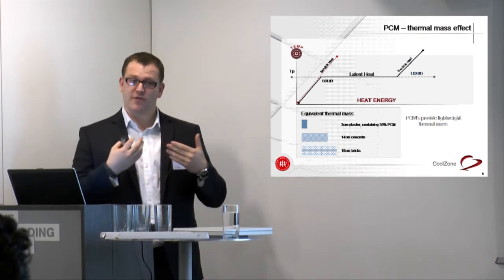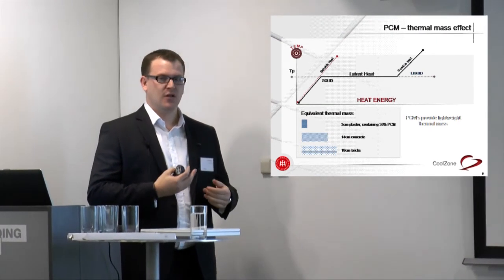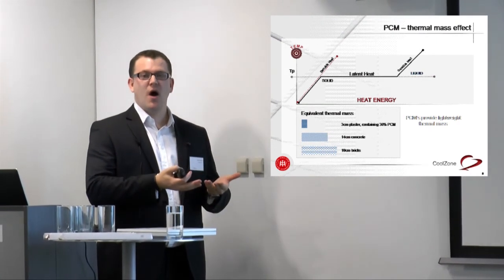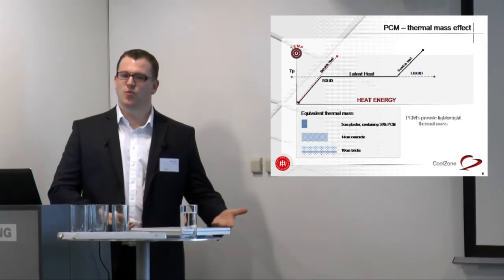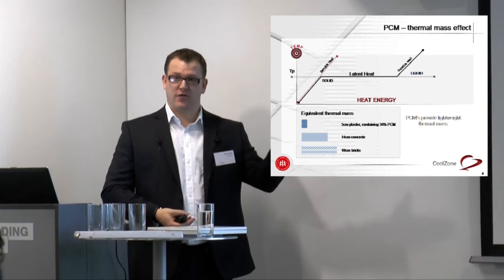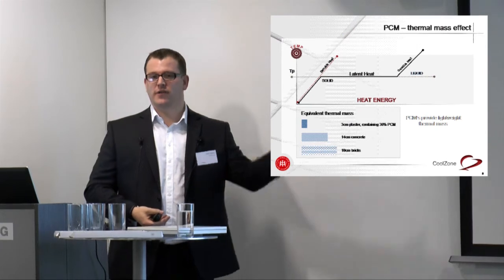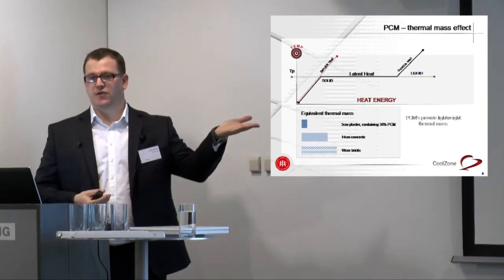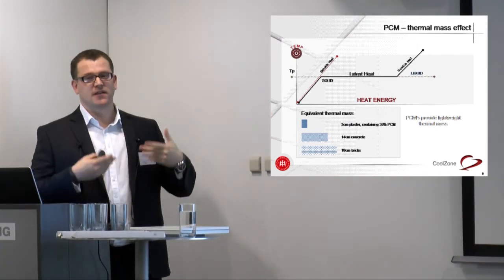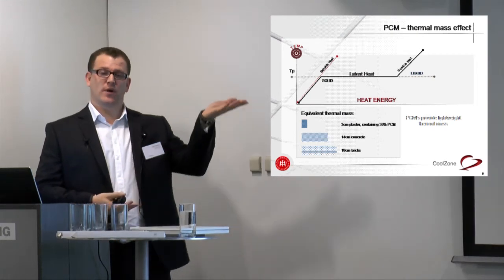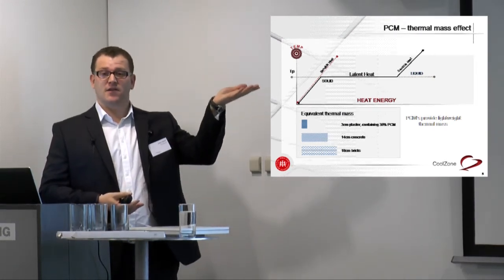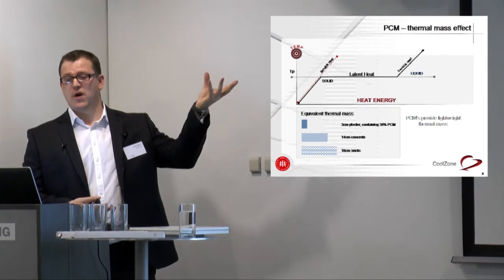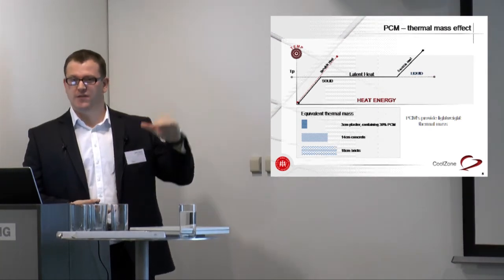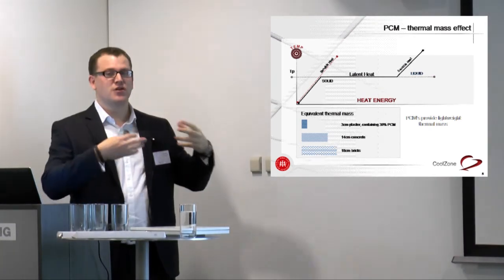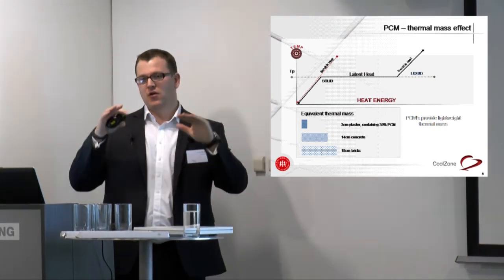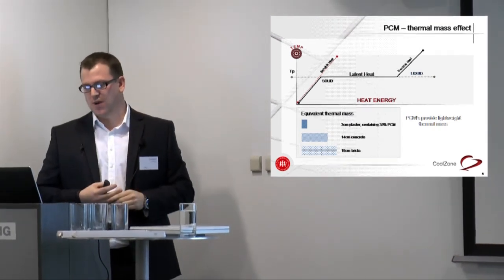And incidentally, if you're heating concrete, getting the room up to temperature, that concrete is absorbing heat all the way through, so from 5 degrees up to 20 degrees for your set points. And likewise, if the room overheats, the concrete's absorbing it. So if it overheats and gets to 30 degrees, that concrete may stay at 30 degrees for longer before it gets a chance to cool down. So you have to purge the whole of the concrete all of the way to reduce the temperature.